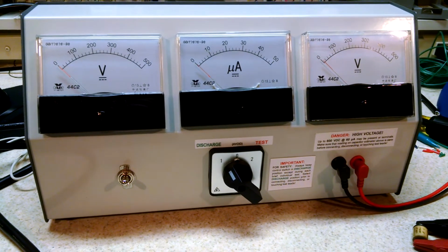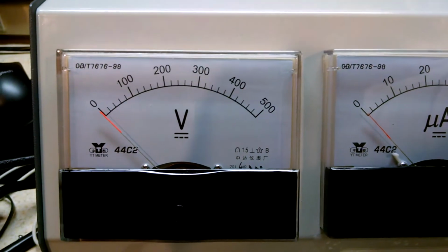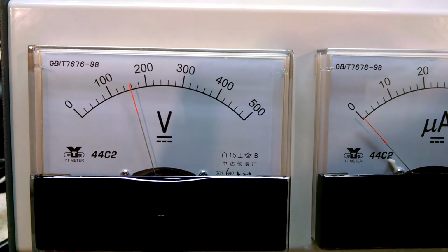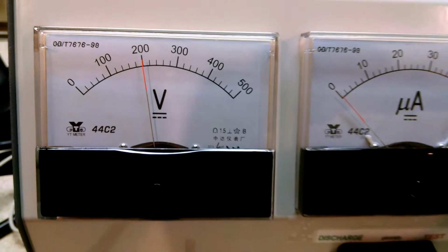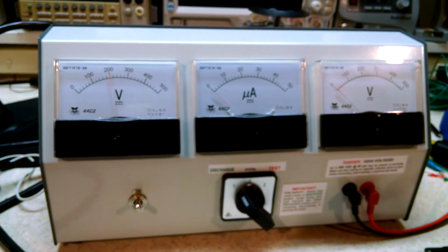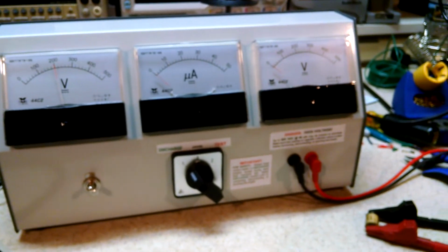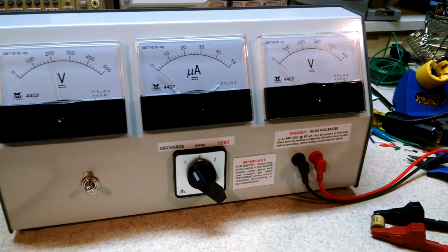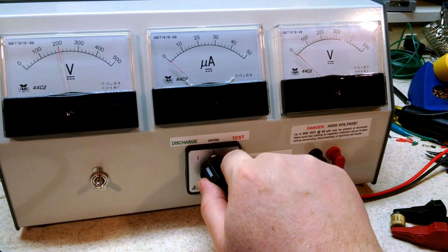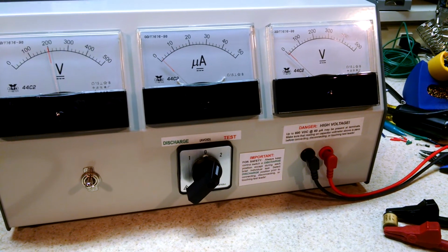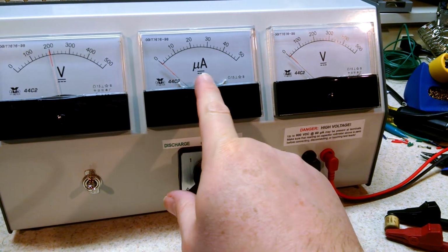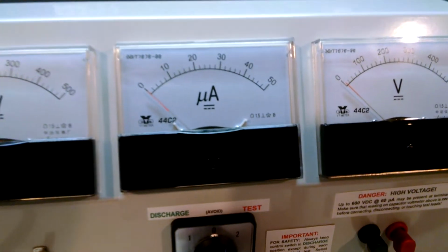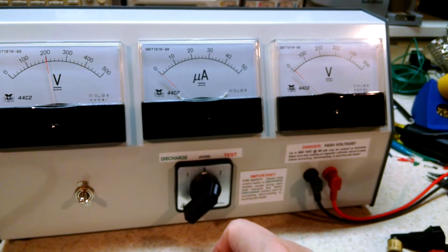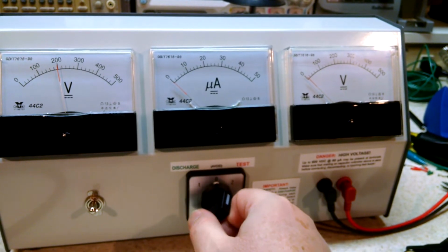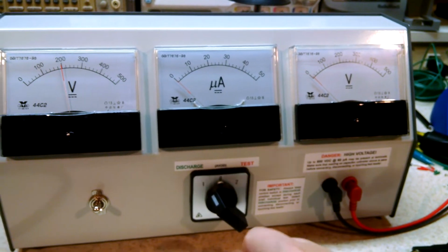Alright, so we'll do the same test now. We'll start up with 200 volts on this guy. Again, this capacitor is rated for 600 or so volts. Alright, please focus. There we go. And I'll throw the switch here. And there we see that the leakage current went back down to 0. Try that again.